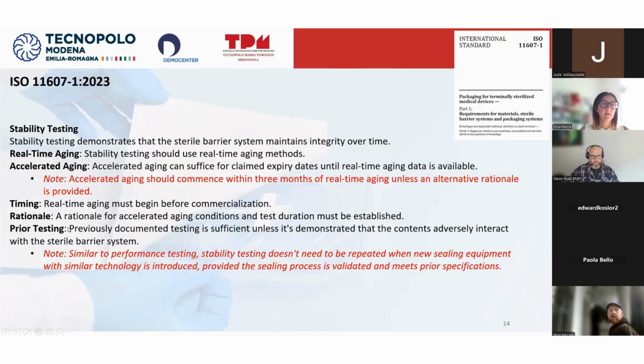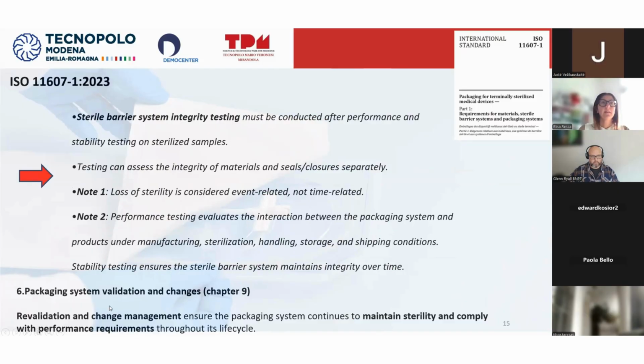Prior testing: previously documented testing is sufficient unless it is demonstrated that the contents adversely interact with the sterile barrier system. So, the sterile barrier system integrity testing must be conducted after performance and stability testing on sterilized samples, and the testing can assess the integrity of the materials and seals/closures separately.